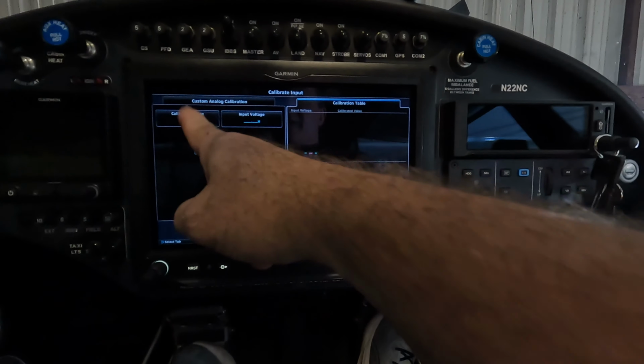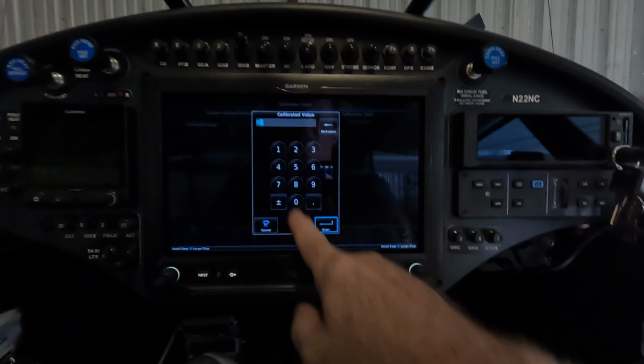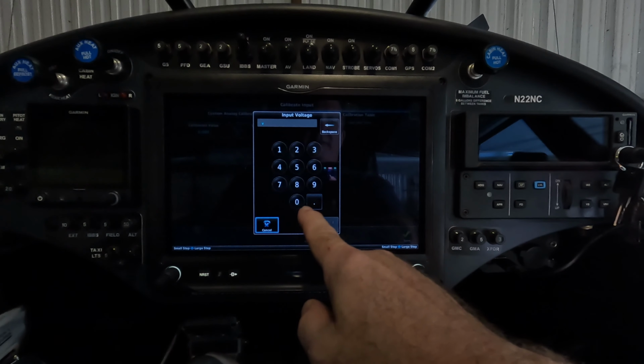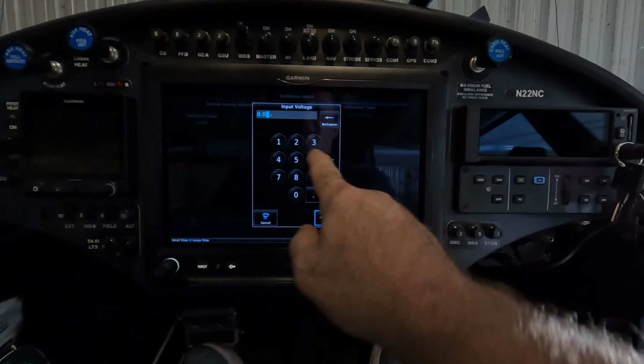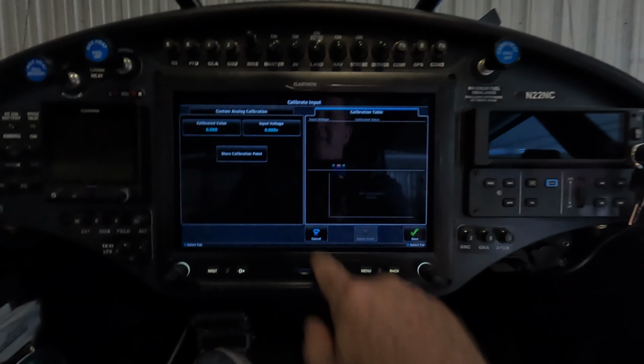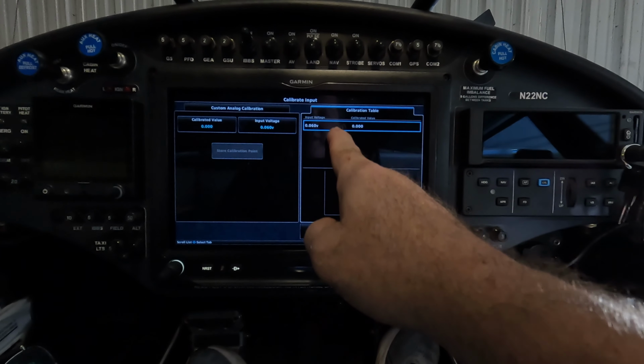And now I'm going to set calibrated value of 0 parts per million as 0.06 volts. Now I'm going to store the calibration point.